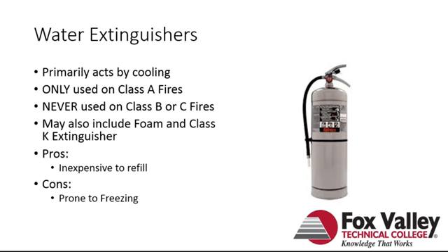The pros of water extinguishers: they're very inexpensive to refill. Basically, you fill it up, you take an air compressor to the end, charge it up, and you're done. The cons: they are prone to freezing, and they're kind of limited in what they can do. You've got to be in a place where there are Class A hazards, but not B or C, in order to make these effective. So they are good, but there are a lot of limitations as well.